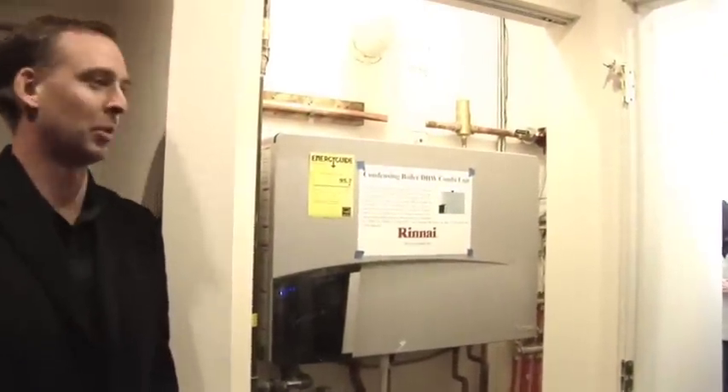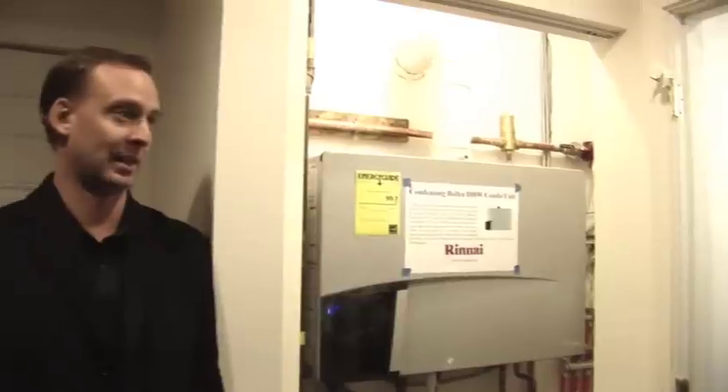Rinnai makes the most efficient residential condensing boiler that's available, so this is about the best you can get. Your water heating is going to be up in the 90s on efficiency, as well as heating the house. It does have a 5 to 1 turn down — so we're at 175,000 BTU at most, but it will modulate down to 20% of that at a minimum firing rate.